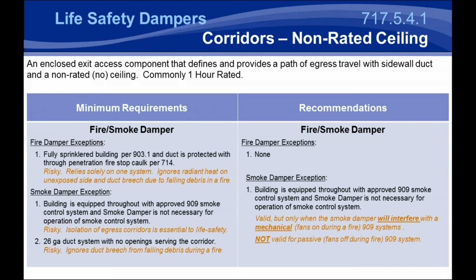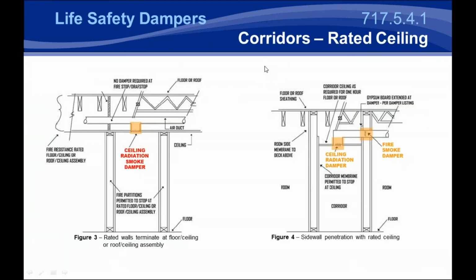Now, if you've got 26 gauge duct that runs above a corridor that doesn't serve the corridor, there are no openings to the corridor, you don't need a smoke damper or fire damper as part of the protection. And while on the surface that seems like a reasonable trade-off, we do think it's also risky because of that duct breach type of occurrence that could puncture that duct and allow smoke to get into a corridor that it wasn't intended to, because there's no penetration, there's no protection of that penetration. So typically for corridors, we recommend the minimum fire smoke dampers.